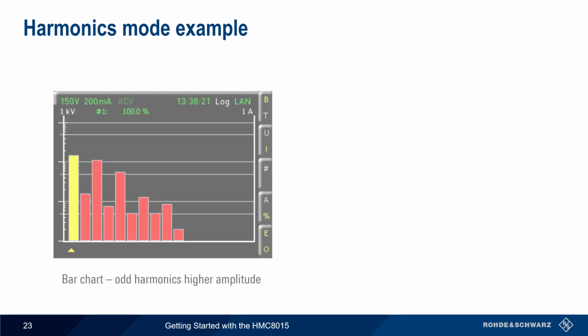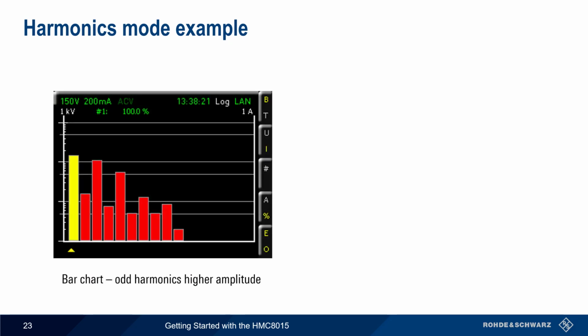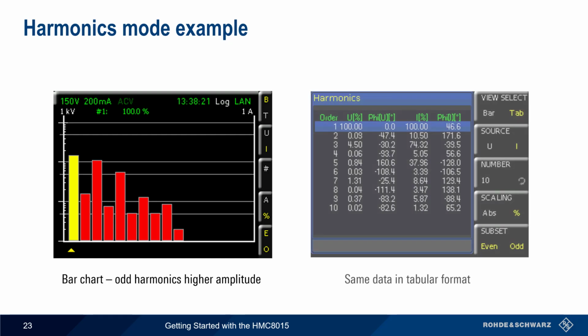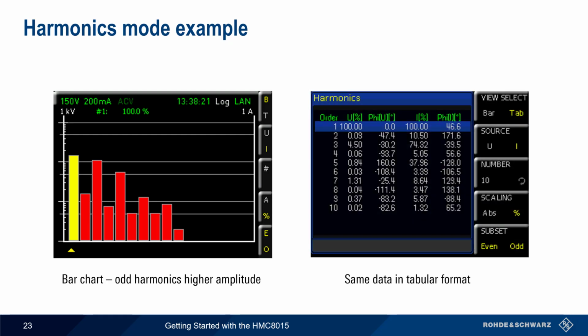The bar chart display is useful in visualizing patterns, such as the much higher amplitude of odd harmonics compared to even harmonics in this example. Bar chart mode only shows amplitude, so tabular mode is needed if we want to see the phase angle in degrees for each individual harmonic.